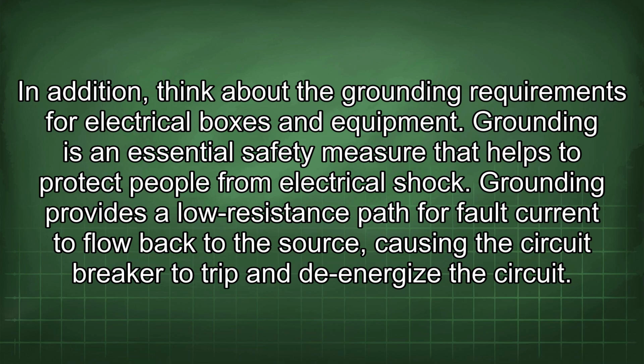In addition, think about the grounding requirements for electrical boxes and equipment. Grounding is an essential safety measure that helps to protect people from electrical shock. Grounding provides a low resistance path for fault current to flow back to the source, causing the circuit breaker to trip and de-energize the circuit.